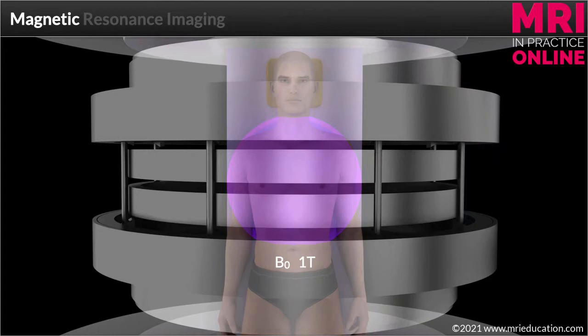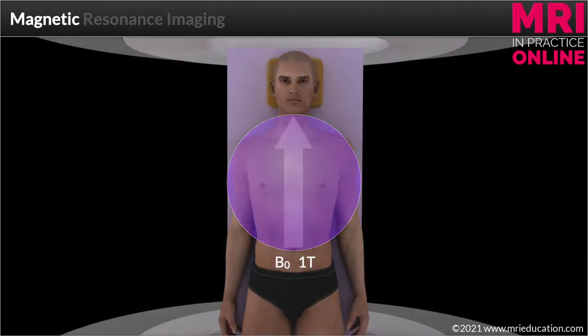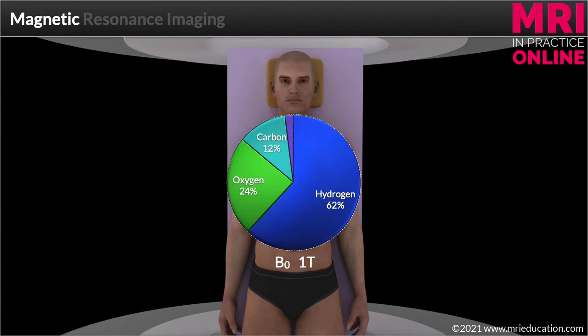Right at the center of the scanner there is an area where the magnetic field is very homogeneous. This can be visualized as an approximately spherical volume 40 to 50 centimeters in diameter, across which the field strength varies by less than 5 parts per million. It's at the center of this imaging volume that the anatomy of interest is positioned. This volume of tissue consists mainly of carbon, oxygen and hydrogen. Hydrogen is the most common element in the universe, accounting for approximately 75 percent of everything that exists, and because of the high water content in the human body about 62 percent of the atoms are hydrogen atoms. This is a factor known as proton density.